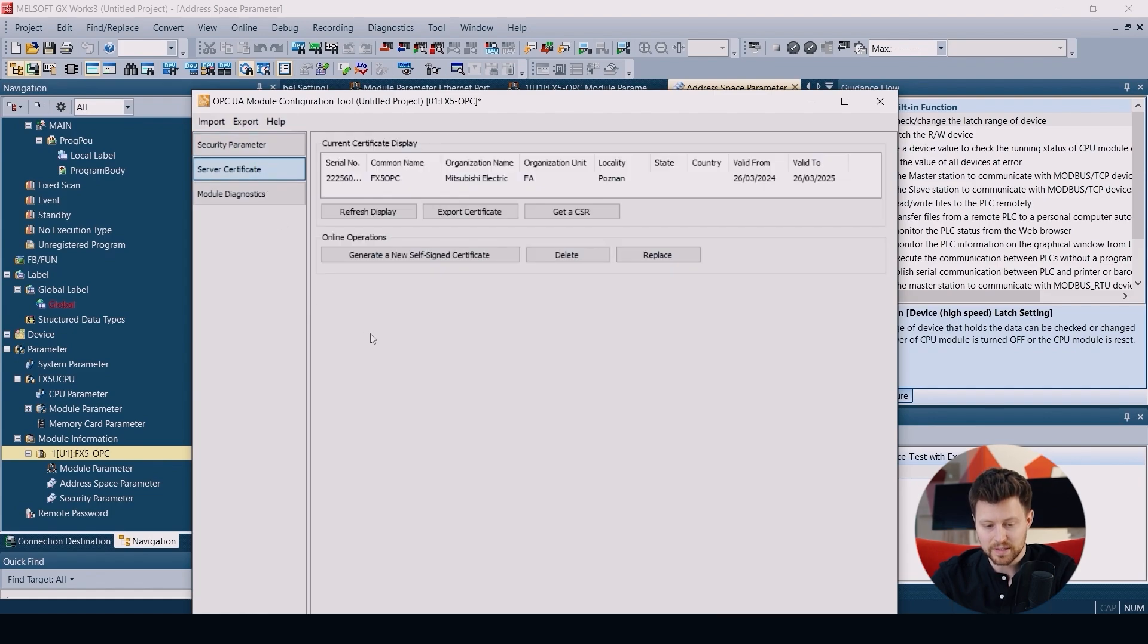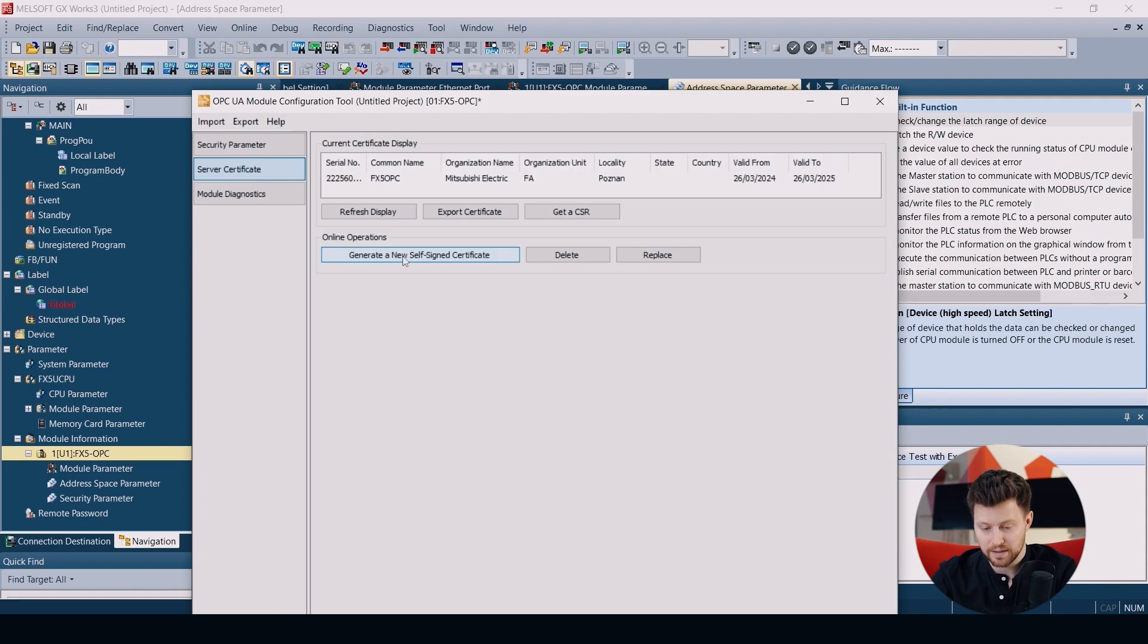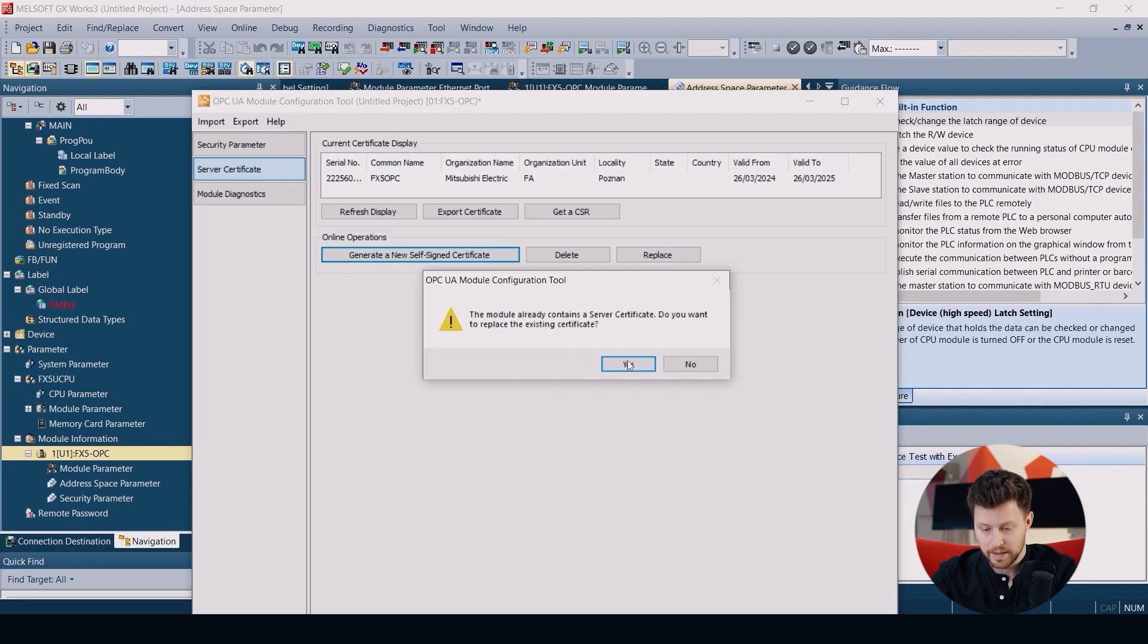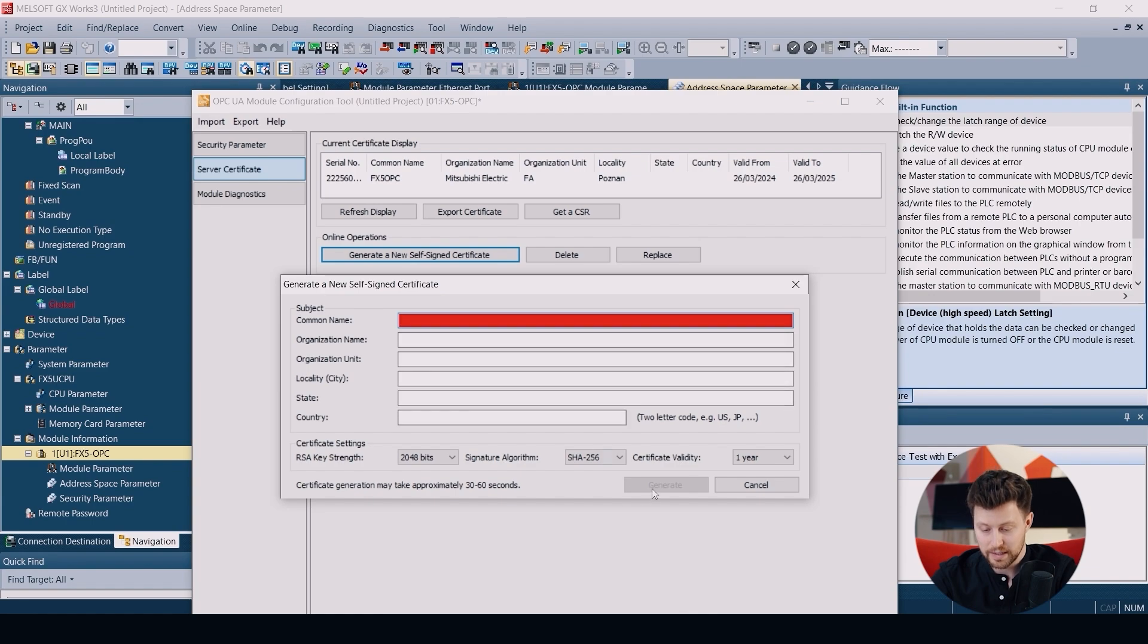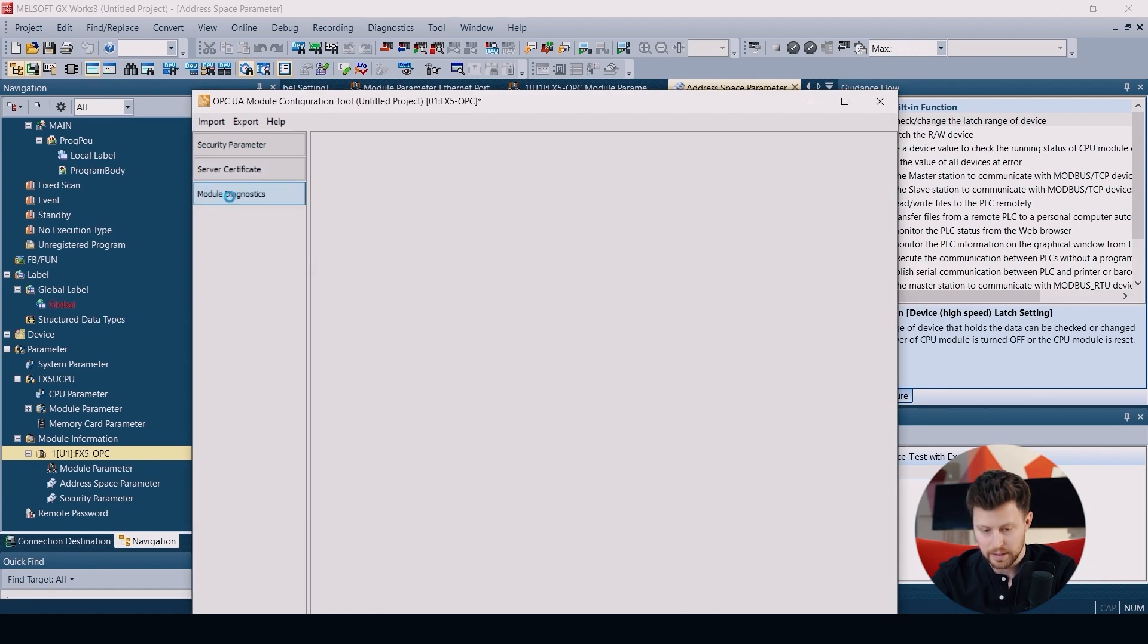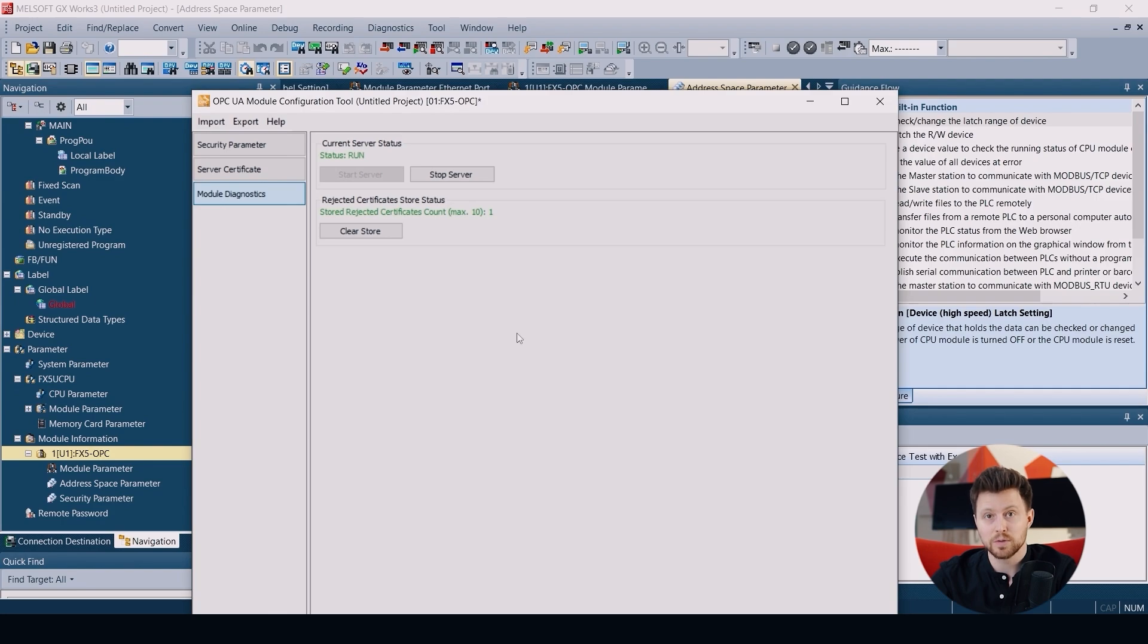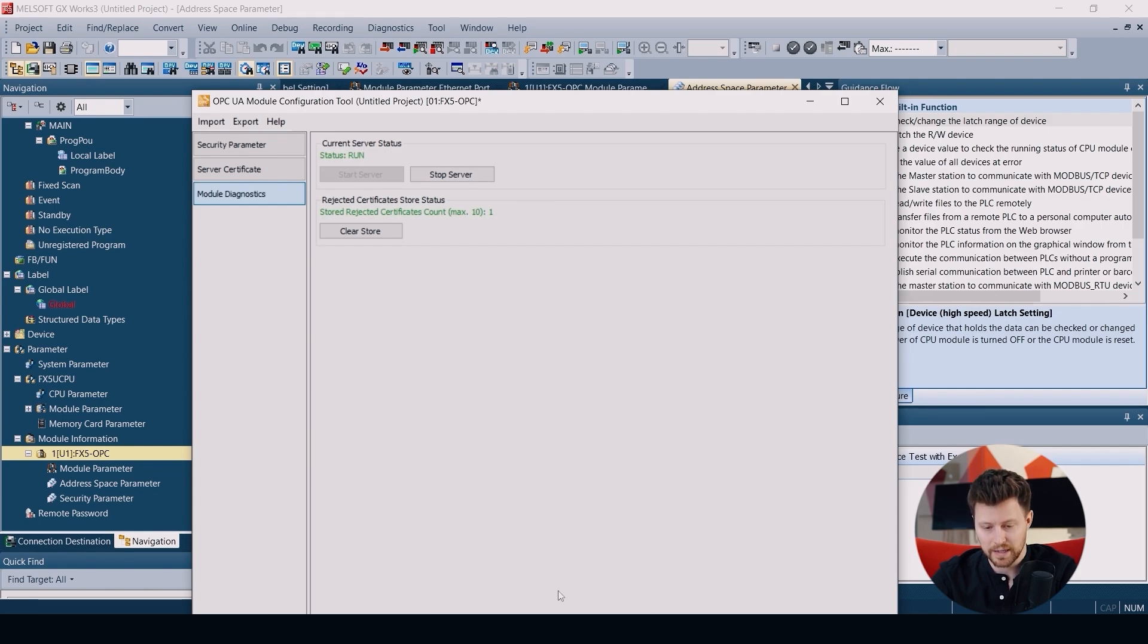Now let's open the server certificate. I already prepared one, but if you want to generate a new, please click generate a new self-signed certificate. Here click yes, and here we just put our data and click generate. We can also see the module diagnostics here. So we can see that our server is running, so we should be able to connect this with our OPC client.